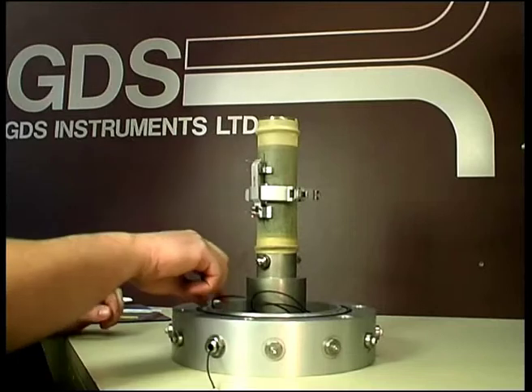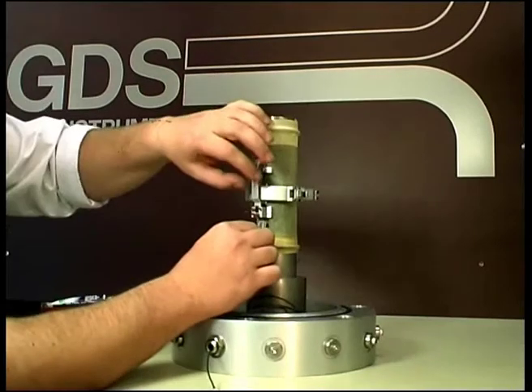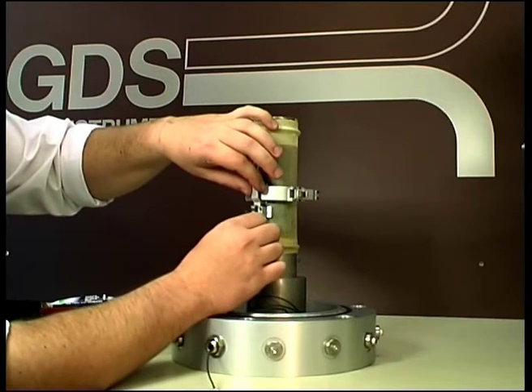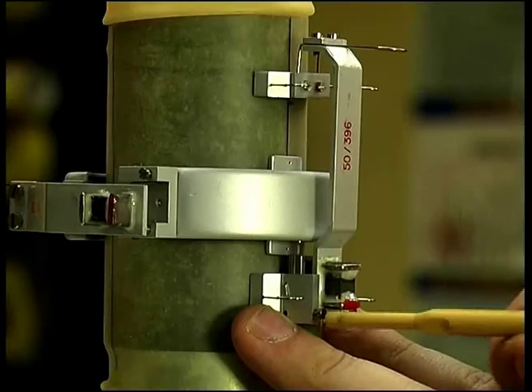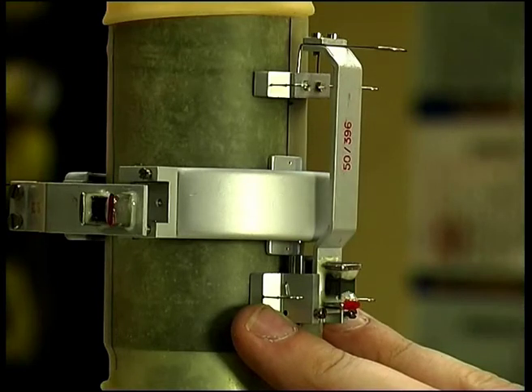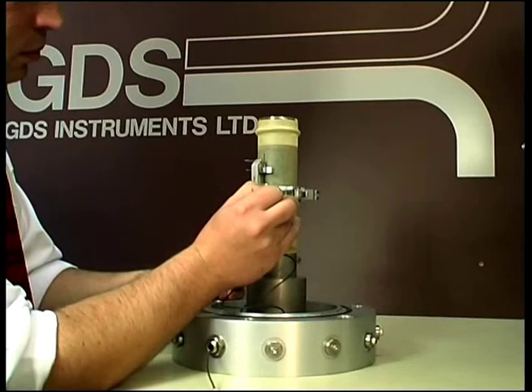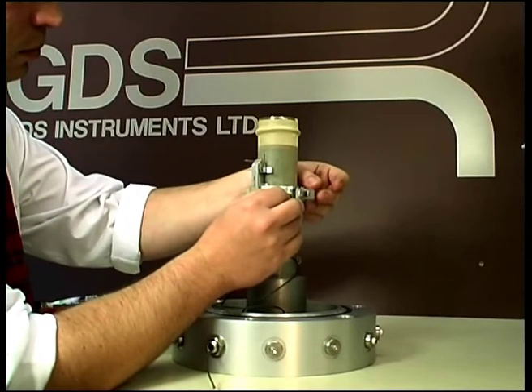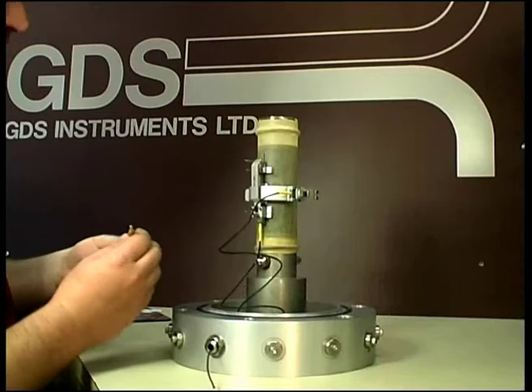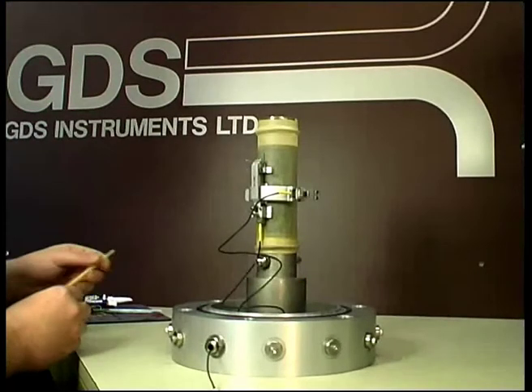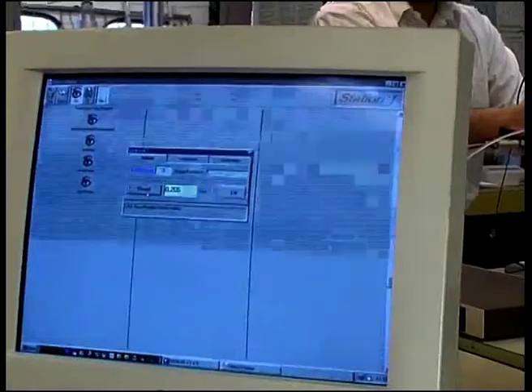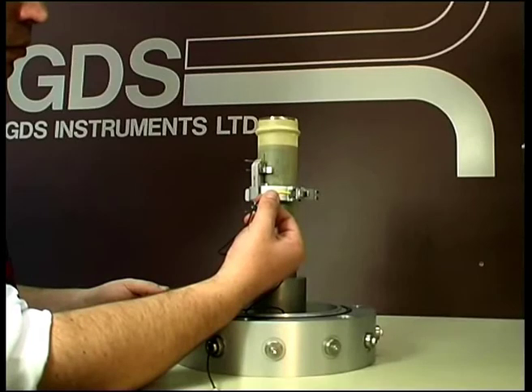Now we can insert the chips and tighten the screws very carefully. We only want to tighten the screws pinch tight as we will be moving the chips again in a moment. Now, while we are reading the output from the chips, either on our data logger or PC, we should move the chips relative to their magnets to the so-called zero gauss position, where the voltage will be zero.